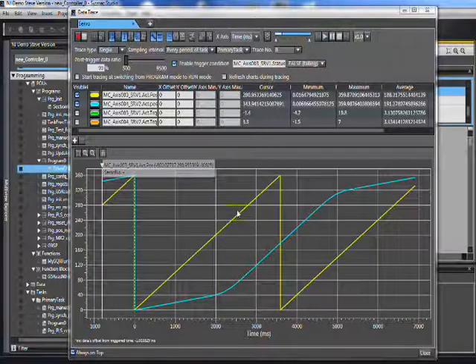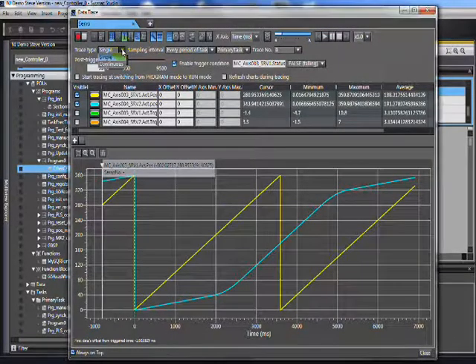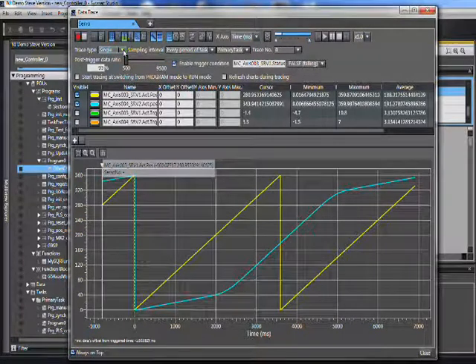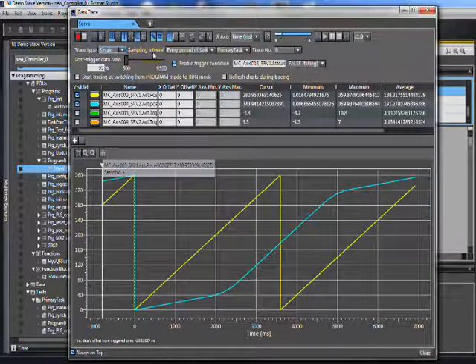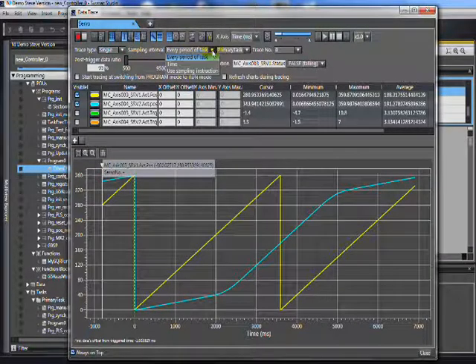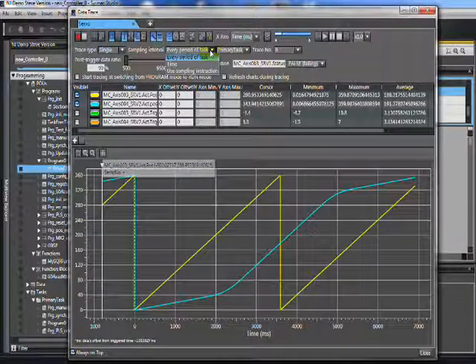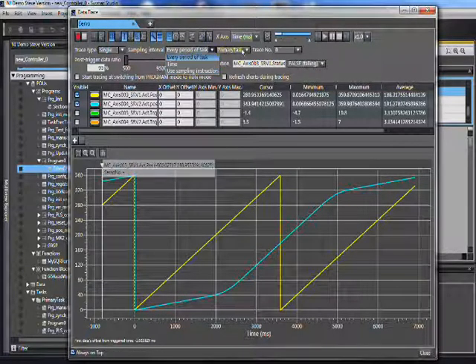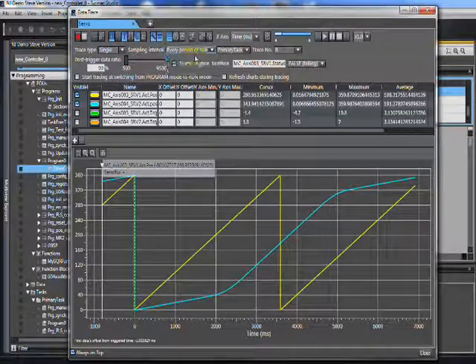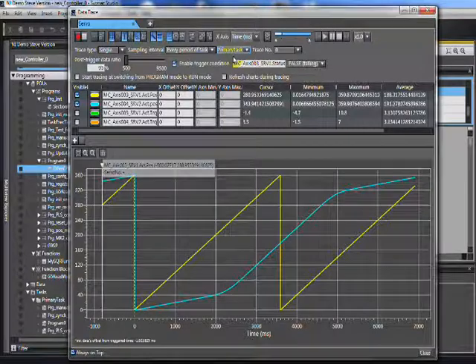Now I want to tell it how fast to log — that's here. I can pick single or continuous. I'm going to pick single in this one; I'll do continuous in a different video. The sampling interval I can set by the period of a task, by time in milliseconds, or by using an instruction in the PLC telling it when to log. This of course could be sub-scan. If I pick task, I have to tell it which task, and if it's motion it would be my primary task.